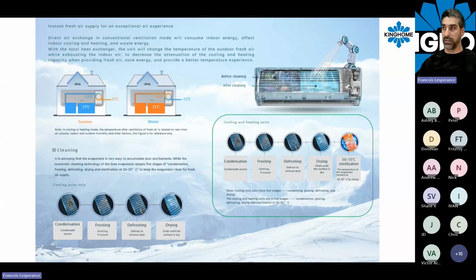What it's going to do is trap all the dust and the dirt on the coil. The next step will be to achieve a fast defrosting. So now the unit will change from cooling to heating mode, and we're going to heat up the coil to make sure all the ice will melt and every dust and dirt will fall down into the drain pan.